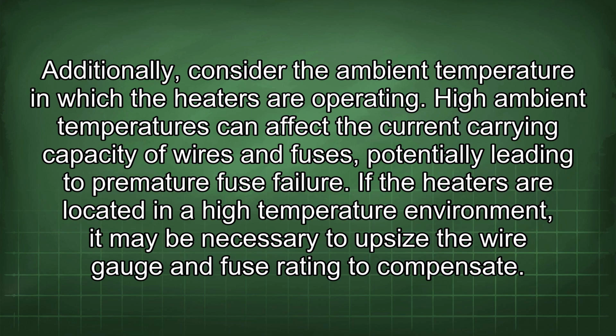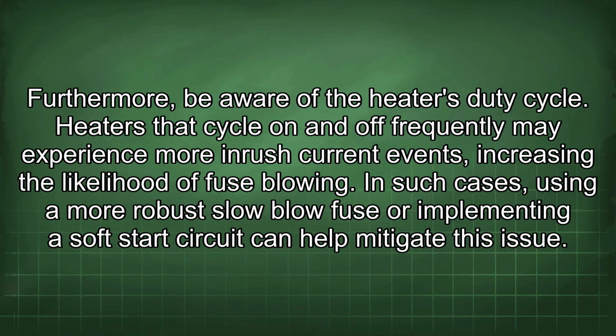Additionally, consider the ambient temperature in which the heaters are operating. High ambient temperatures can affect the current carrying capacity of wires and fuses, potentially leading to premature fuse failure. If the heaters are located in a high-temperature environment, it may be necessary to upsize the wire gauge and fuse rating to compensate. Furthermore, be aware of the heater's duty cycle. Heaters that cycle on and off frequently may experience more inrush current events, increasing the likelihood of fuse blowing. In such cases, using a more robust slow-blow fuse or implementing a soft start circuit can help mitigate this issue.